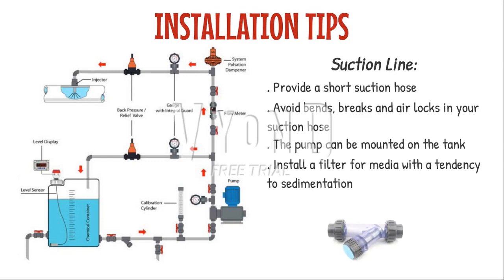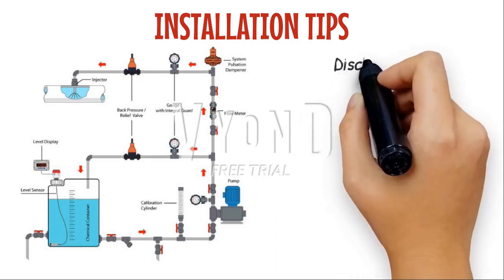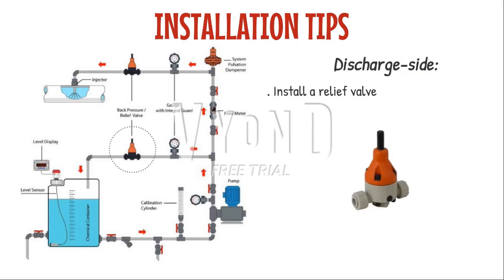Construct the suction line with a filter for media that tends to settle, keeping the suction valve a few millimeters above the potential level of sedimentation. Install a calibration cylinder to allow precise site calibration and evaluation of a pump's output for discharge. Installing a relief valve right after the pump discharge will shield the dosing pump in the discharge line from excessive pressure buildup. The counter pressure at the injection point and the dosing medium's pressure at the pump suction valve must have a positive pressure difference of at least one bar; if this cannot be assured, install a pressure loading valve in the discharge line.